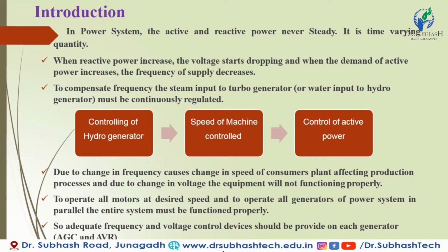Motor loads are mainly affected by change in frequency. When the frequency lowers, the generator speed gets lower and produces less work for the customer load. A 1% drop in the frequency results in a 2.5 to 3% drop in the output of the motor. At lower frequency, turbine blades can get damaged. At a lower value of frequency, core losses in the transformer become large and the transformer core goes into the saturation region.